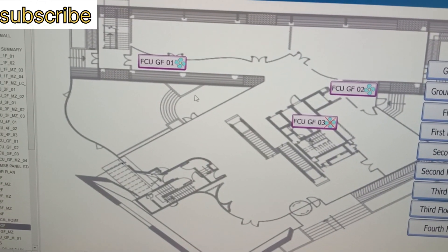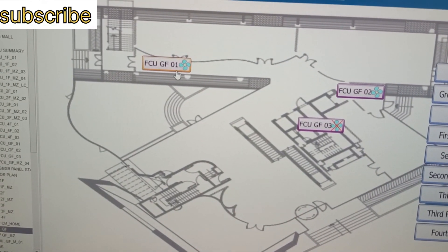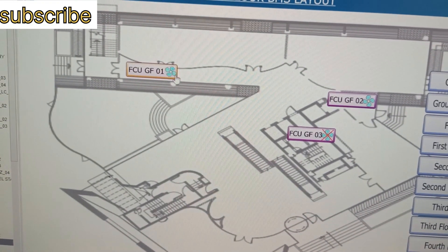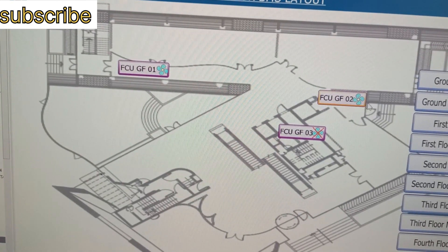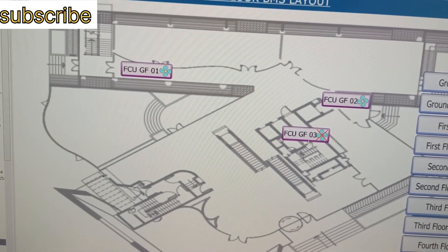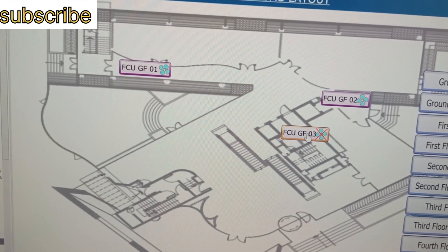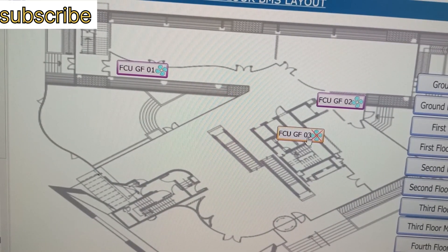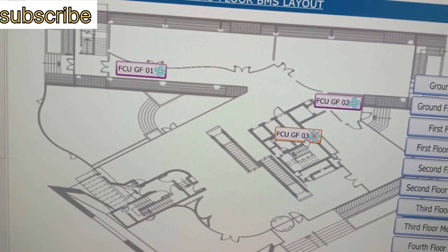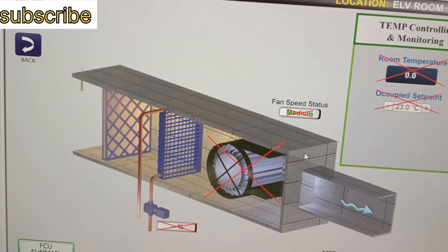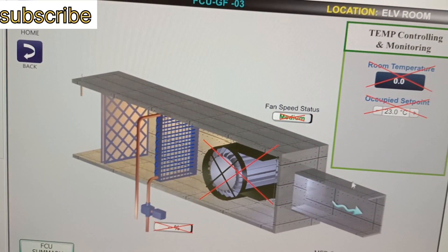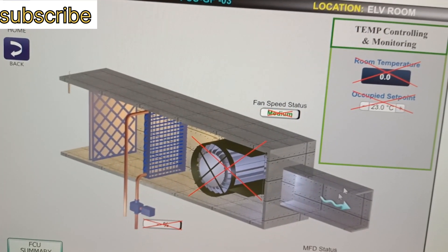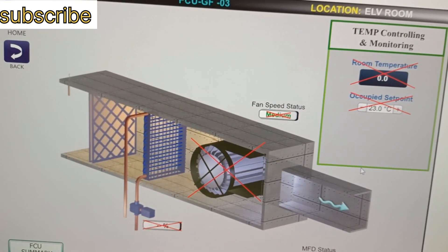On the ground floor we have three FCUs. FCU1 is running and FCU2 is in off position. FCU ground floor 3 is showing a cross, meaning there is no signal coming from the thermostat to the DDC panel, so we are not getting any reading.